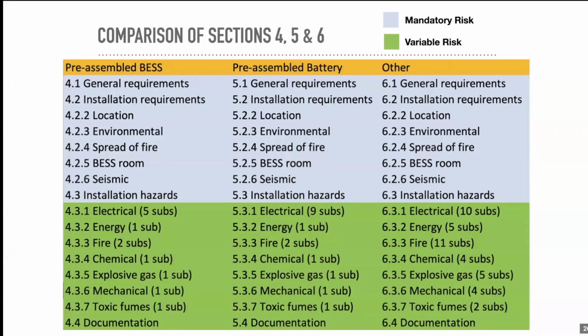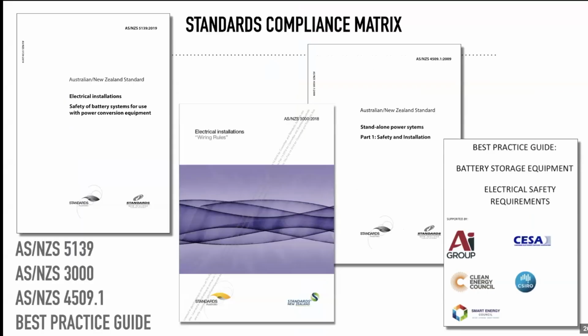So remember a previous slide, I said the best practice guide, if I just go back to that, was a collection of standards. It isn't a standard itself, and it refers to international standards like IEC 62619, UL 1973, and others. Those are means to achieve a high level of safety. And because it's not a product standard, it's not something that you necessarily get tested at a lab, the manufacturer needs to deem compliance to it. But within it, it has product standards. So ironically, a manufacturer to comply with the best practice guide probably has to achieve compliance for various substandards within that. So to be part of the best practice guide, you actually need to have a lithium-ion battery. And the reason I say lithium-ion is that currently the best practice guide only deals with lithium-ion batteries. I know this is a major concern for all those other chemistries on the market, but it was kind of like the first stab at trying to come up with a product standard.